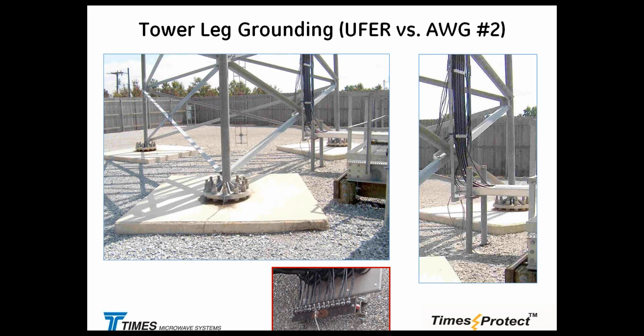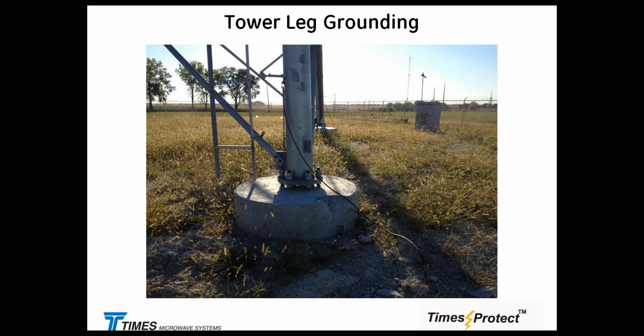Well, here is an example. This is not too good a picture. I apologize, guys, for it, but somebody has decided to put, probably that looks like 250 MCM, or tough to say, I didn't get the description of the type of wire. And they have decided to put the ground lug for the tower leg very high, and here is a little grounding rod, okay? So they wanted to make sure that they divert the current from the tower leg and it's going to go to that one grounding rod.